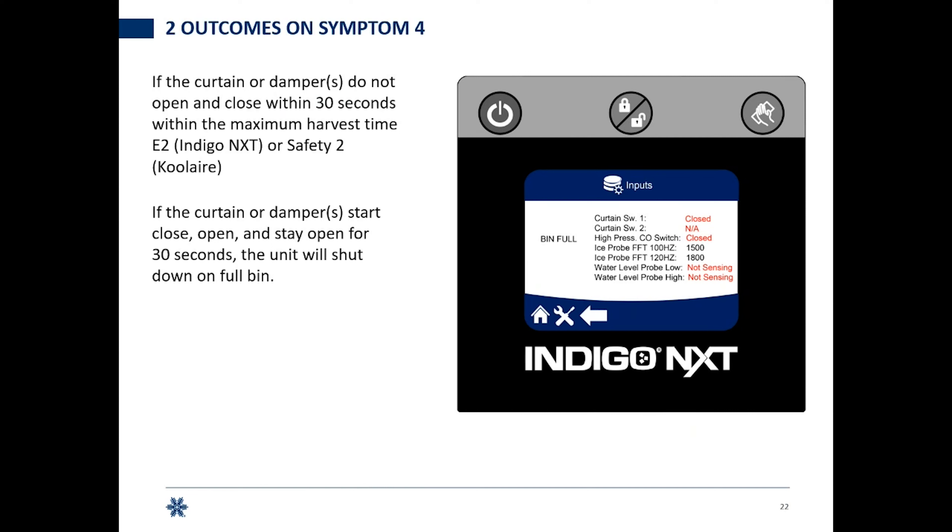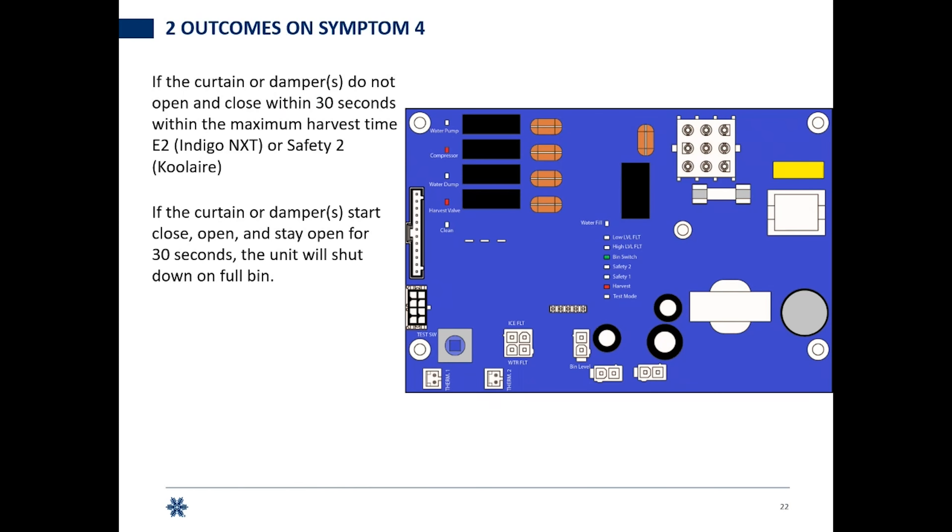There's a delay involved — we need the curtain to be closed and to have gone through the delay. On the Koolaire control board in harvest, you can see the compressor and harvest valve are running, the harvest light is on, and the bin switch light is lit, telling you the bin switch is made and the curtain is closed. When the bin switch light goes out, you have 30 seconds to get the ice off and the curtain closed. If it doesn't happen, you go off on full bin. Full bin delay on Indigo Next is five minutes; on Koolaire it's three minutes.